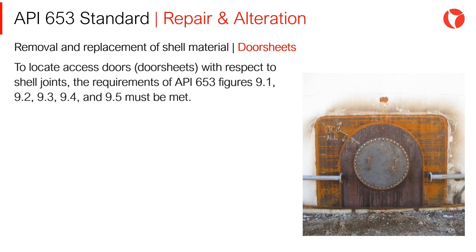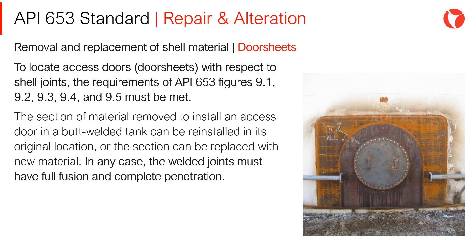Door sheets: to locate access doors with respect to shell joints, the requirements of API 653 figures 9.1, 9.2, 9.3, 9.4, and 9.5 must be met. The section of material removed to install an access door in a butt-welded tank can be reinstalled in its original location, or the section can be replaced with new material. In any case, the welded joints must have full fusion and complete penetration.